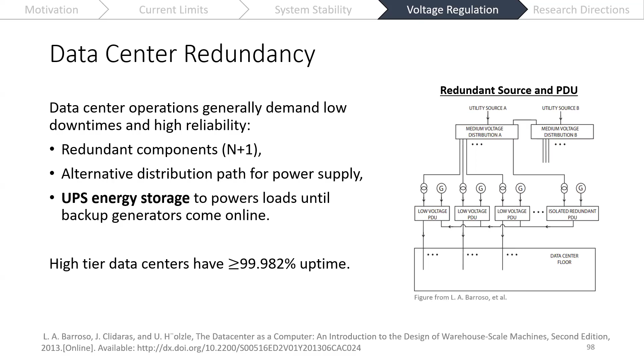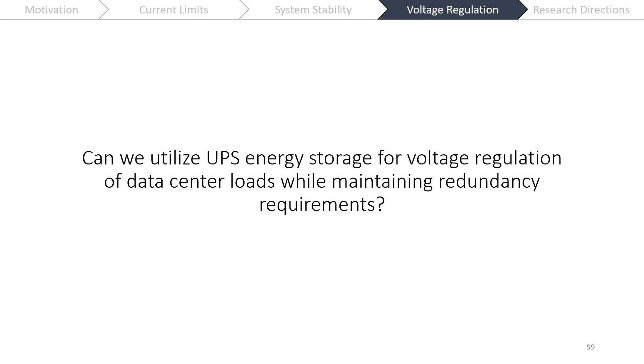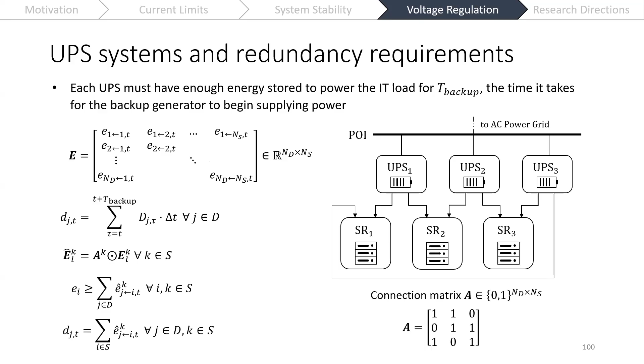So the question that we ask here is, can we utilize the energy storage in these uninterruptible power supplies for voltage regulation of data center loads while maintaining the redundancy requirements to be able to satisfy that load for whatever that backup time is? To go about looking at this question, the first thing we did was formulate these constraints, essentially saying how much energy we need to provide from each uninterruptible power supply to the server racks, based on how the uninterruptible power supplies are connected to the server racks.